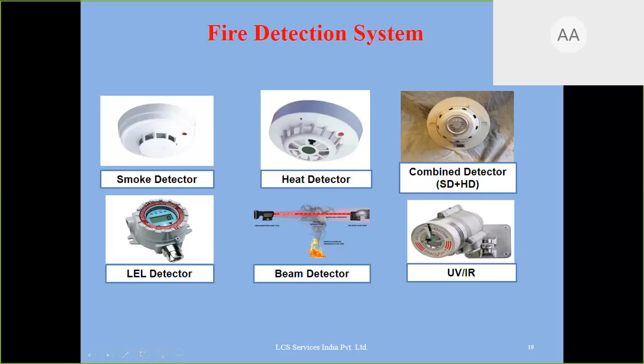Next is the LEL detector. LEL means lower explosive limit. It is installed on any gas, right? What does LEL mean? Every gas has LEL and UEL, lower explosive limit and upper explosive limit. For example, if I take LPG, most companies use LPG in the pantry or canteen. So LPG, liquefied petroleum gas, has an LEL of 1.8%. Until LPG is present in the air at 1.8%, there will be no fire because the LPG is very thin, right? And UEL is the upper explosive limit. The upper explosive limit of LPG is 9.6%. If there is LPG more than 9.6%, then also there will be no fire. Fire will take place between LEL and UEL. Correct? 1.8 to 9.6.